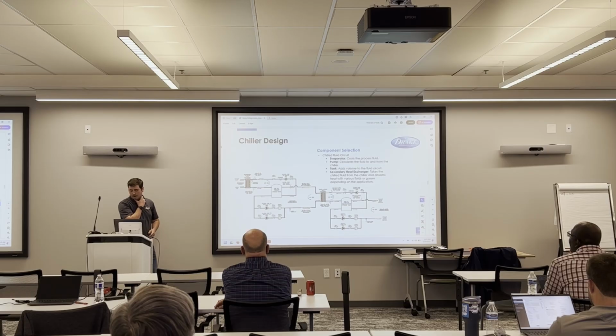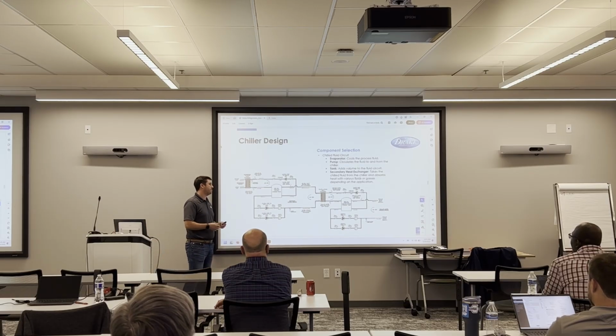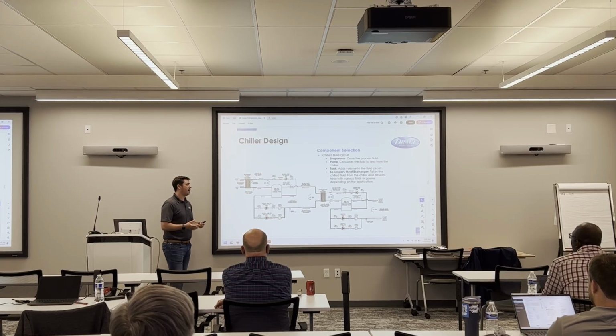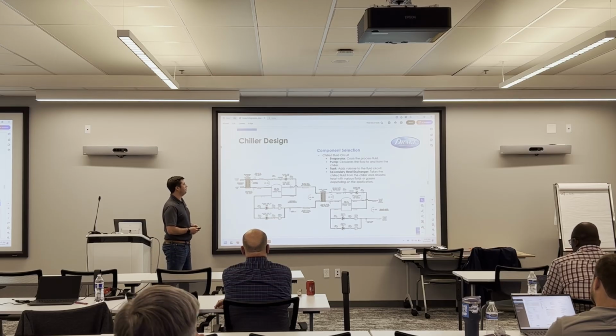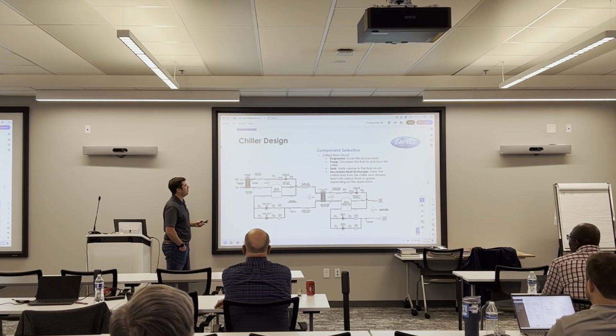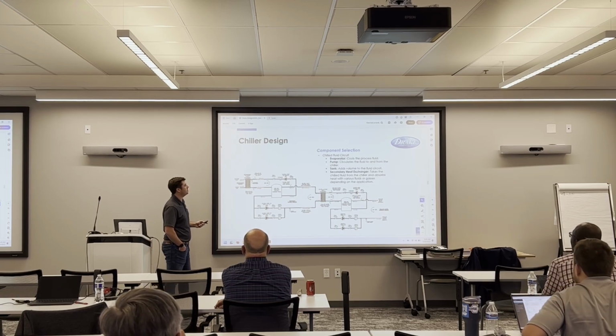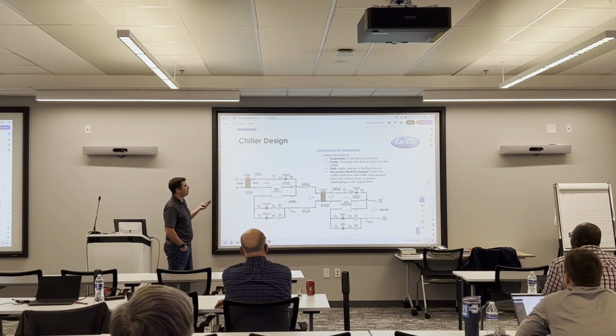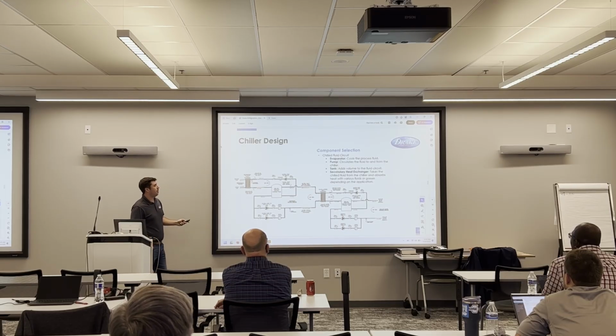All right, so chillers just aren't refrigeration. So it's not just compressors, and condensers, and evaporators. You got to worry about the chilled fluid circuit as well, the hydronic circuit. With a chilled fluid circuit, there's a couple items to note. Obviously your evaporator, that's your cooling medium, that's what's cooling your process fluid. You're going to need pumps just to circulate the fluid to and from the chiller.